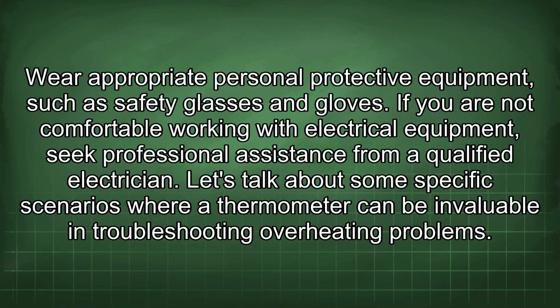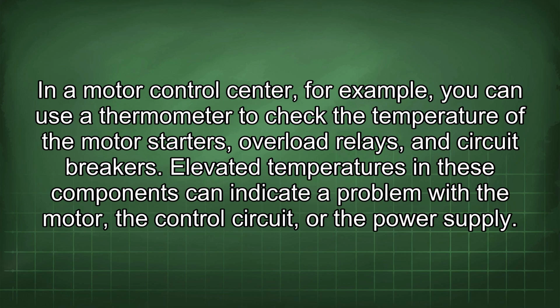Let's talk about some specific scenarios where a thermometer can be invaluable in troubleshooting overheating problems. In a motor control center, for example, you can use a thermometer to check the temperature of the motor starters, overload relays, and circuit breakers. Elevated temperatures in these components can indicate a problem with the motor, the control circuit, or the power supply.